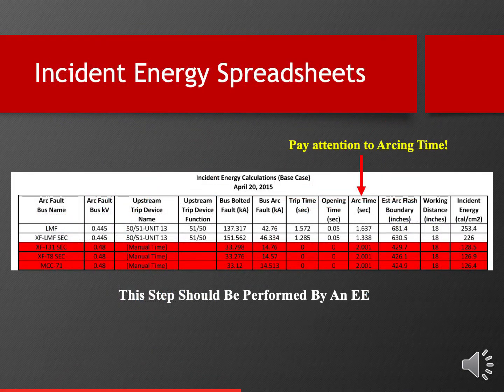Now, what you see here is an incident energy calculation spreadsheet. Something that I recommend that we engineers do, which is what I've done here, is I've sorted the data for the customer in descending order from incident energy, but I've also highlighted things in red where the breaker timed out. And what I mean by that is, take a look at the little arrow there. I've got, pay attention to arcing time. The 1584 calculation methodology normally says we're going to limit the calculation time on an arcing event to 2 seconds or less.